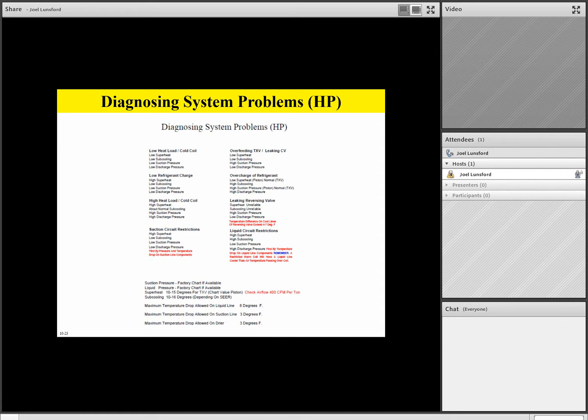So as we take a look at these service calls today, please be sure and have your diagnosing system problems page handy so that we can do these service calls together and you can follow along and see how we can diagnose system related problems just by looking at pressures and temperatures and superheat and subcooling. Let's do another one. Let's say we have a low refrigerant charge. What will that look like? Well, if we have a low refrigerant charge, we'll see high superheat, low subcooling, low suction pressure, and low discharge pressure.